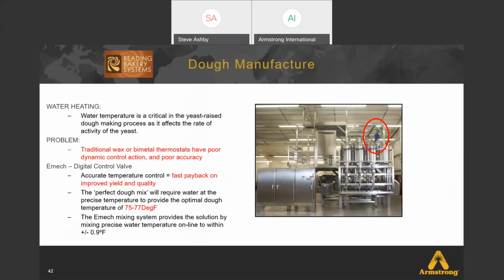We support a lot of bakeries with the Emech valve. You can see there in the right-hand corner of that picture the blue actuator, and this is for water heating, but not necessarily hot water. The water temperature is critical in the yeast-raised dough making process, as it affects the rate of activity of the yeast. A common problem is that traditional wax or bimetal thermostats have pretty poor dynamic control action and poor accuracy. So with the Emech valve, with the accurate temperature control, there's fast payback on improved yield and quality.